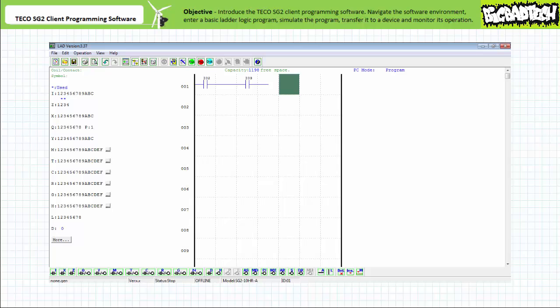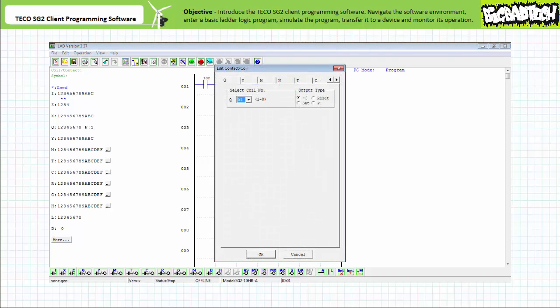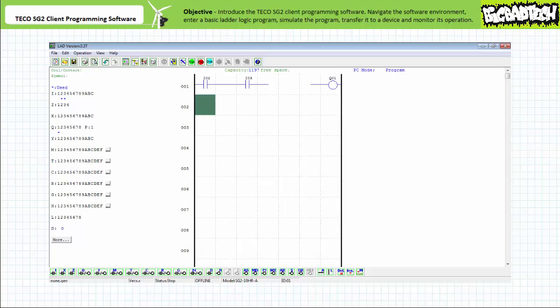Let's add a make instruction examining input I2 — use the pull-down menu to select operand number 2 and press OK. Let's add another make instruction examining input I3 into rung one column C. Note the software is smart enough to realize we want them wired together and inserts a wire in column B automatically. Let's put an output Q1 in rung one column G. A pop-up menu allows the user to select basic properties like operand number or latching behavior. For now let's just select the default coil function for output Q1. However, it doesn't do the wiring for us since it's expecting another contact in rung one column E, so select the horizontal wire drawing tool and insert a horizontal wire there. Our program is a series connection of two make instructions examining inputs I2 and I3, yielding a coil output Q1. One can save this program for later editing and reuse.